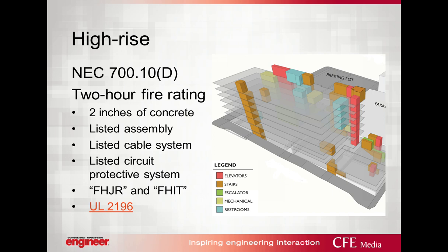Now, the emergency feeders in a high-rise application will be subject to NEC 700.10(D). This section lists options for providing fire protection for emergency feeders. The idea here, of course, is that if I have a fire in one part of the building, I don't want that fire to take out my emergency feeders that serve the rest of the building or another part of the building.